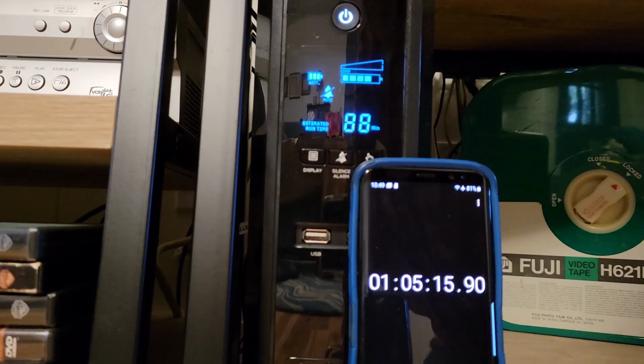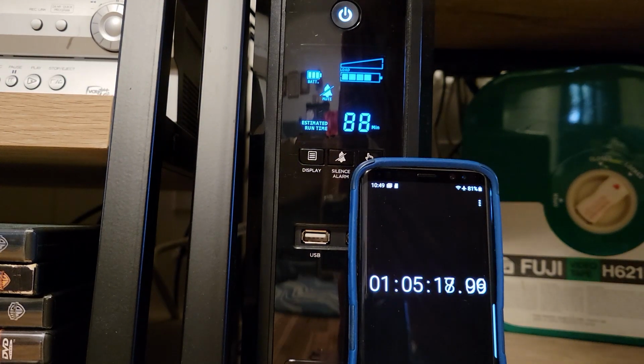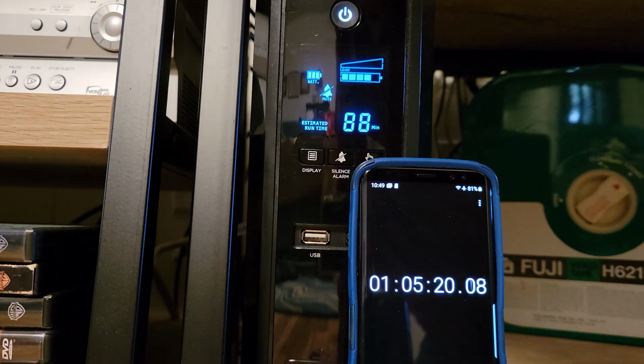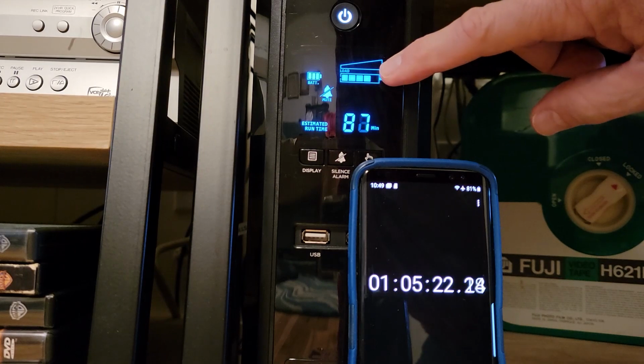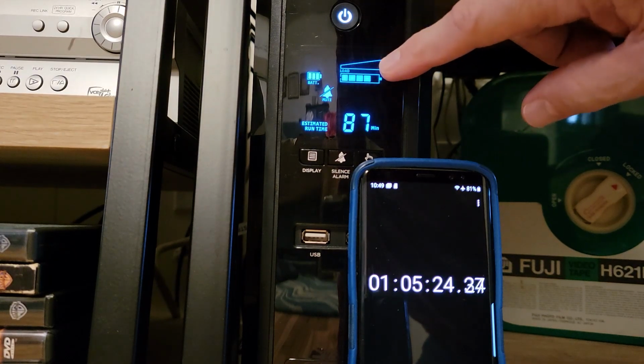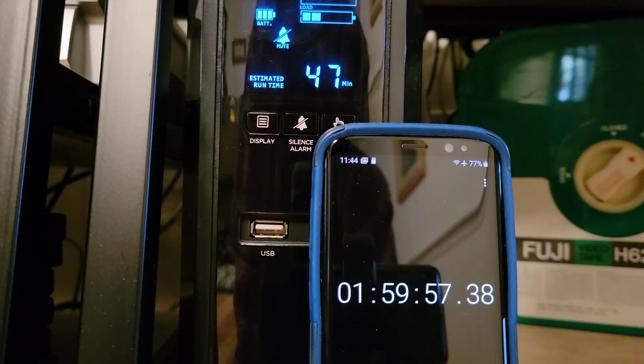45 minutes into the test, we still have 106 minutes left. We're over an hour and 5 minutes, down to 88 minutes left on the battery, and you can actually see the battery level has dropped a notch. We're 2 hours into our test, and we're still showing 46 minutes left on the UPS.